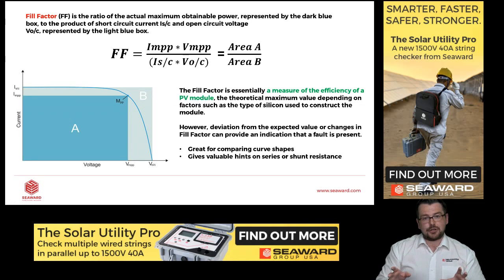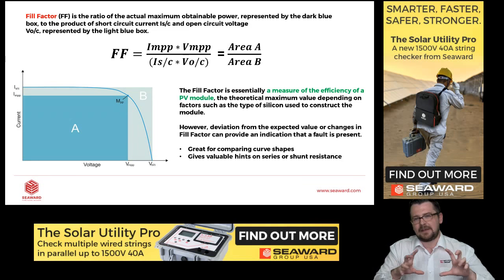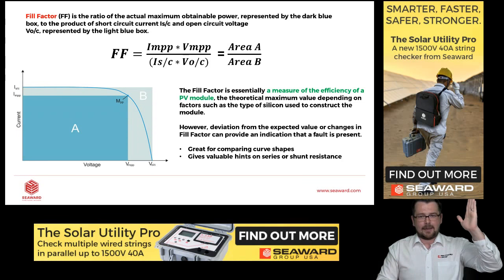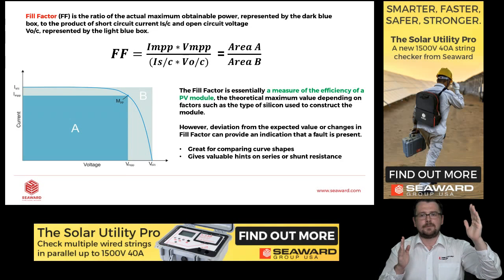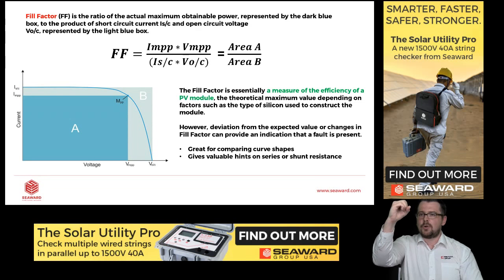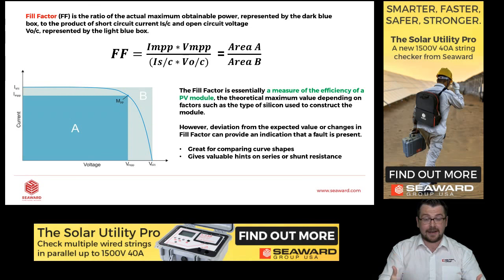So one of the first things we can look at is the fill factor. Now, there's quite a complicated equation on the screen there, and I'm not going to get too bogged down in the scientific theory of IV curve tracing or fill factor, but I can explain this in almost layman's terms. So if we have our IMP, our current at max power point, and our VMPP, our voltage at max power point, this will give us the max power point. So this is where the system should be to operate at its maximum in our measurement.